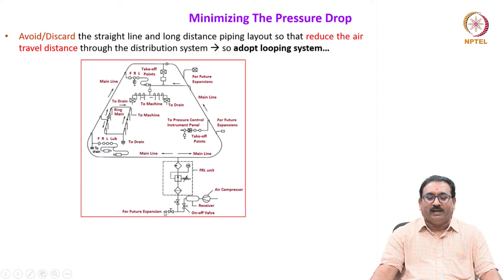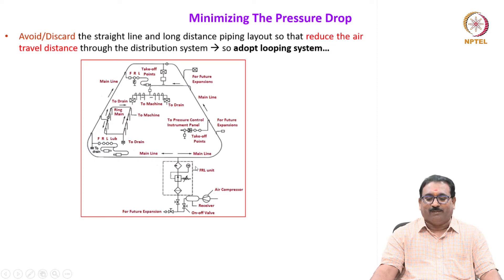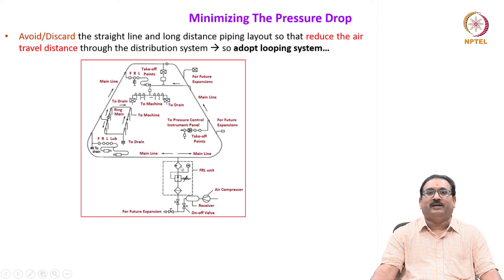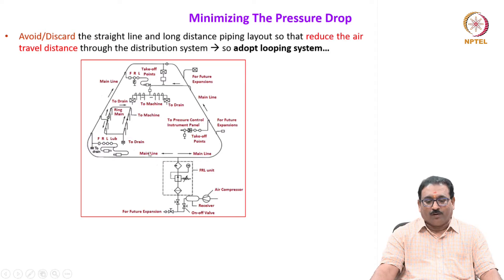Also provide air tapping for future expansion. After the receiver tank, before going to the main line, air will be subjected to secondary air treatment — filter, regulator, lubricator units. Then air will pass to the ring main system, where the air moves through the main line clockwise and anti-clockwise. Then air is tapped to the various stations where the pneumatic devices consume the air.